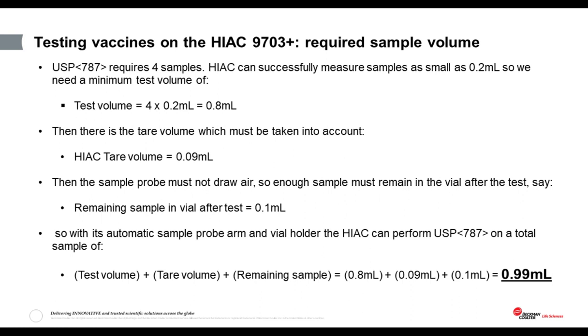And finally, you should aim to leave some of the sample in the vial once the test is completed to ensure that the probe does not pull air in the final sample. So say about 0.1 of a milliliter. Hence, with its automated sample holder, the vial holder, and high accuracy and precision with just 0.2 milliliter samples, the HIAC 9703 can perform USP 787 on vaccine samples with a total volume of just 1 milliliter, or slightly under, in fact.